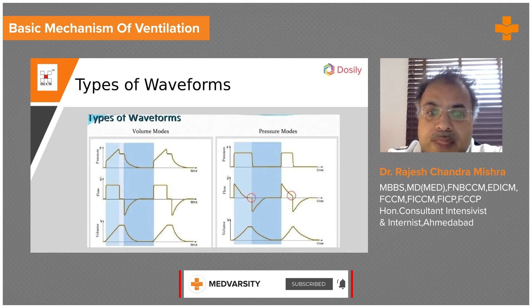Now, a little bit of detail about the pressure versus time, because we need to continuously monitor it. At least this is a basic understanding. When your flow increases, initially the ventilator circuit and airway resistance has to be crossed. Once that resistance is crossed, air will start flowing to the alveoli, and a time will come when it will reach a peak. This peak can be your flow if it is volume control, or this peak can be inspiratory time, depending upon what mode you have selected.